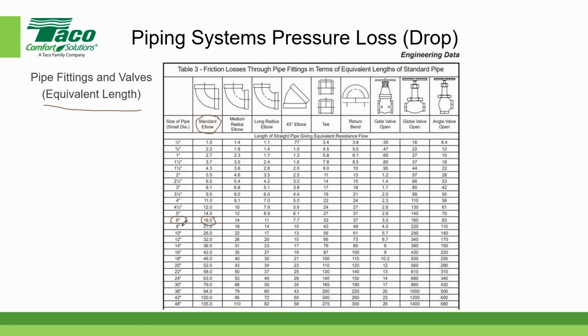And if you'll notice, each one of these different pipe fittings has a different equivalent straight run of pipe. One of the questions I get all the time is, I've got multiple 90-degree standard elbows in my system and I seem to have an excessive pressure drop. What can I do about that? Well, assuming again that you're working from design and you're not trying to retrofit something that's already been built, you might consider going to a long radius elbow instead of a standard elbow. A long radius elbow has a shorter equivalent length of straight pipe. The standard elbow was 16 feet, the long radius elbow was 11 feet. So you can see that can be significant in terms of the equivalent length.